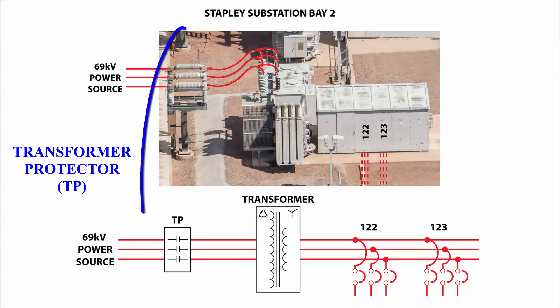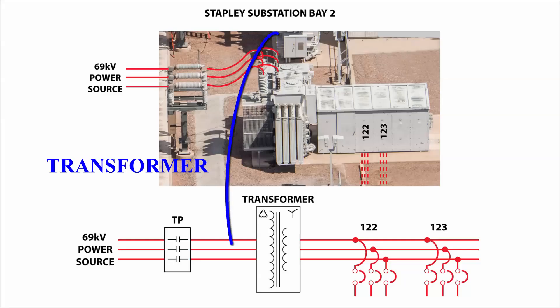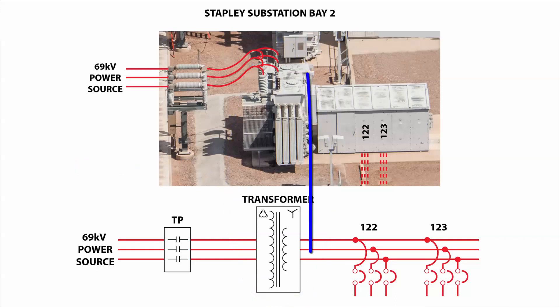The 69 kV source power flows through a transformer protector, which we call a TP. The TP is a low-cost, compact circuit breaker which protects the transformer. The transformer converts three-phase 69 kV power into three-phase 12 kV power. The row of 12 kV circuit breakers is called switchgear.